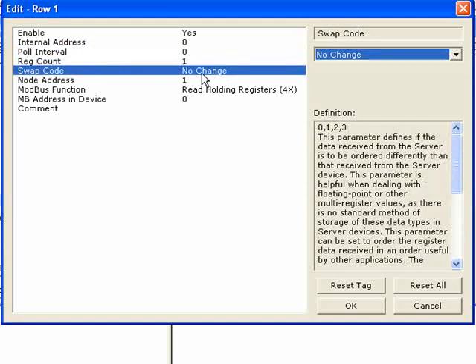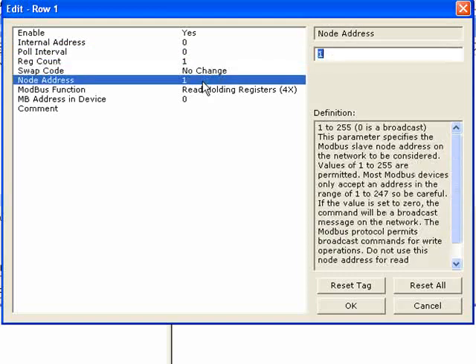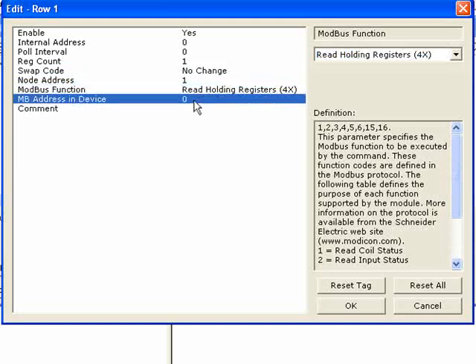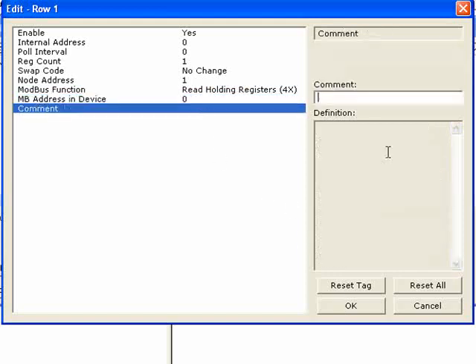The swap code allows you to swap the bytes, swap the words, or swap both words and bytes. The node address is the node address for the Modbus device this command will communicate with. The Modbus function code defines what function will be executed — what kind of data will be written or read from the device. Modbus address in device is your Modbus register within the device — for instance, if reading holding registers 4x, it reads from the 40,000 range. You can also give the command a comment so you know what it's doing.